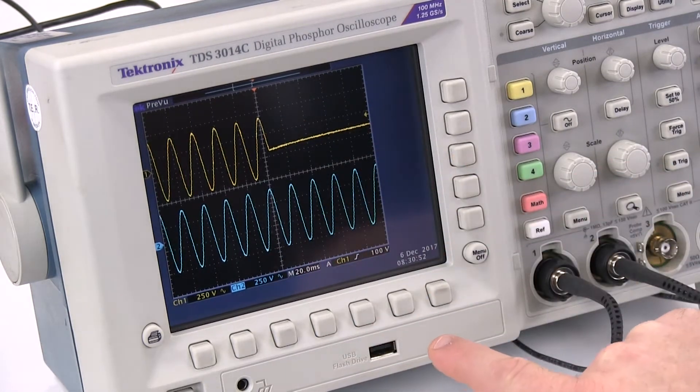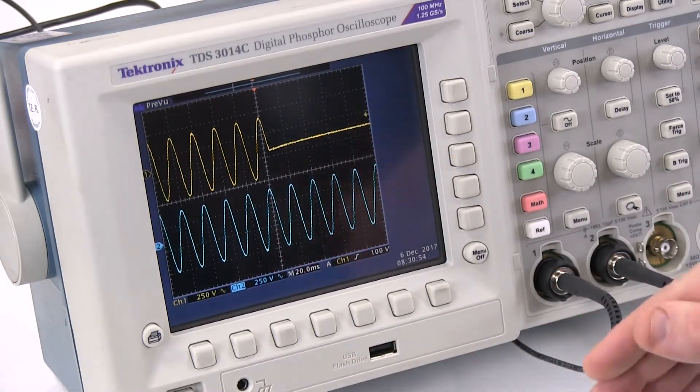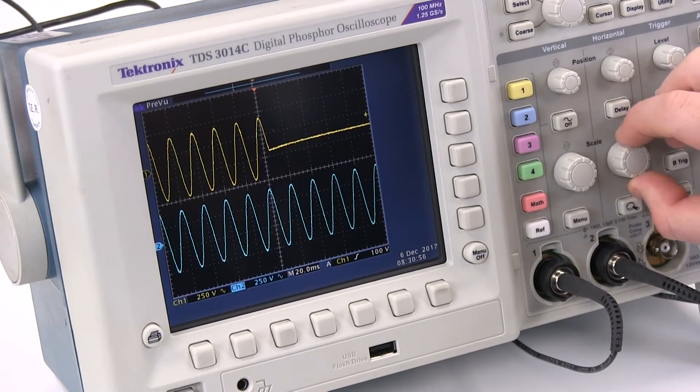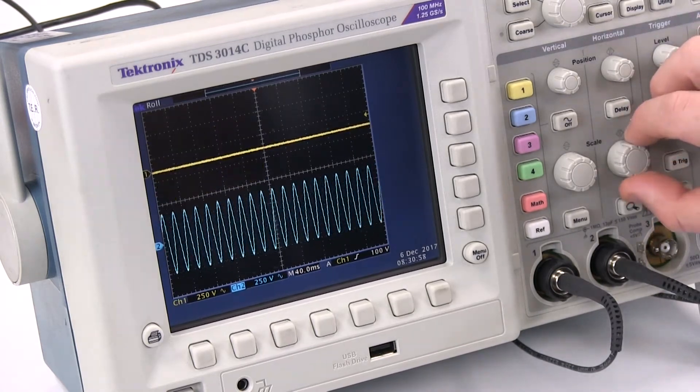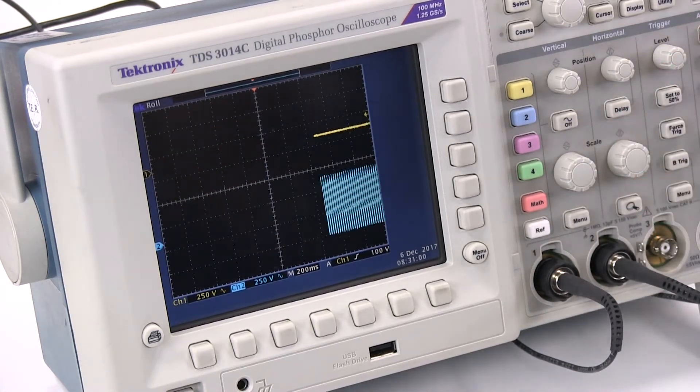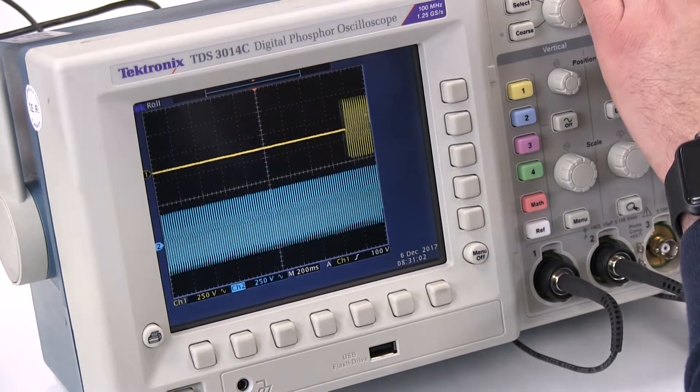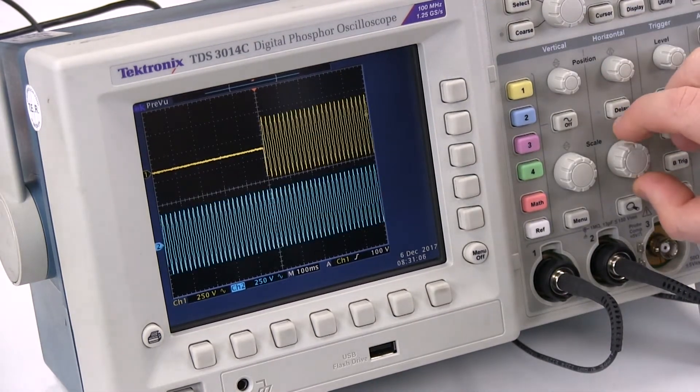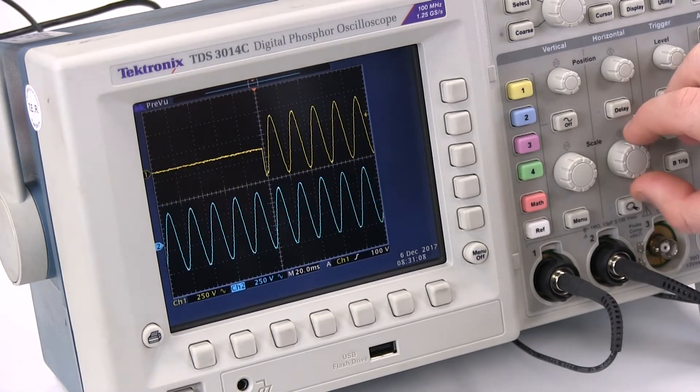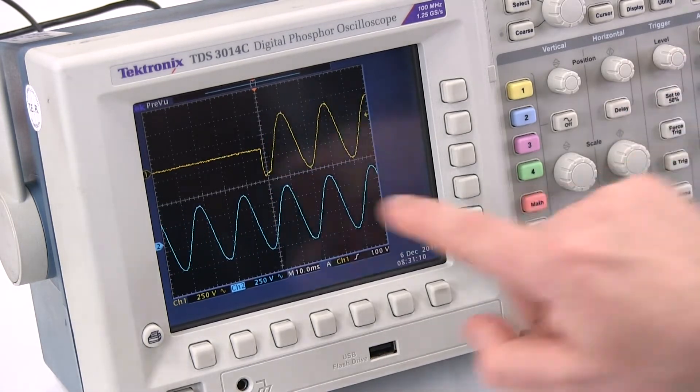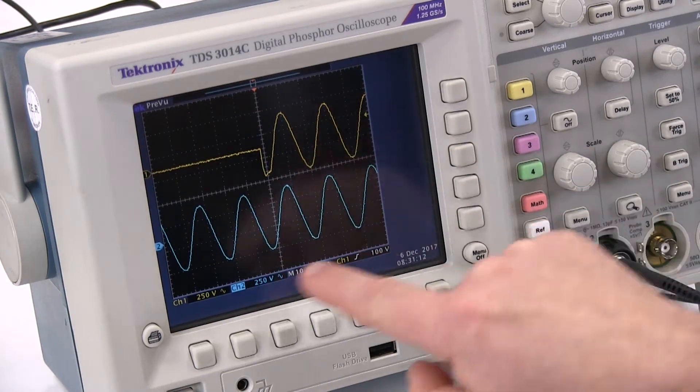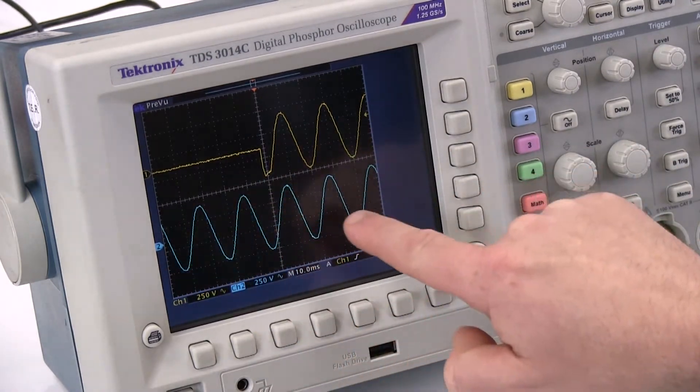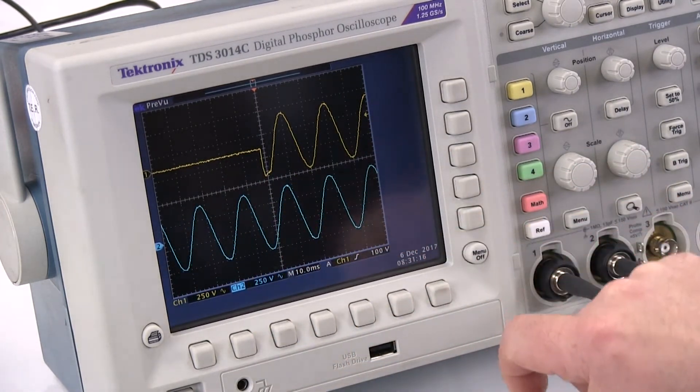Now if I reverse that process in that we return the main supply back onto the UPS, if I slow down my trace once again and reapply that main supply and again stop the trace, if I zoom into that trace again, even though the main supply is returned, the output voltage waveform from our UPS system remains completely unaffected.